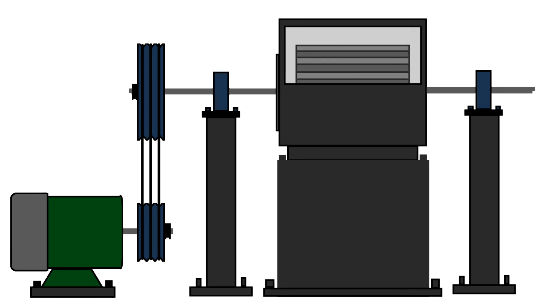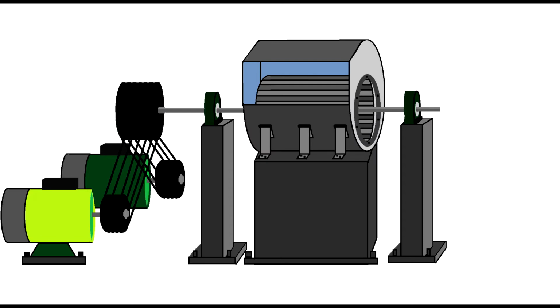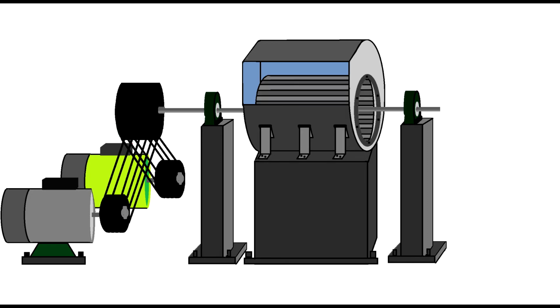If you take out the cover of the AHU, you'll observe the plummer blocks, the pulleys. You'll observe better how the system works. You'll even see the shaft. But that's not enough. Let's go 3D. To have redundancy, we use two motors. If one of the motors gets broken, the other one should take over, like in this case. If this motor has an electrical fault, the programmable logic control will swap the motors and the other motor will continue. But the first motor will be pulled by the second motor.